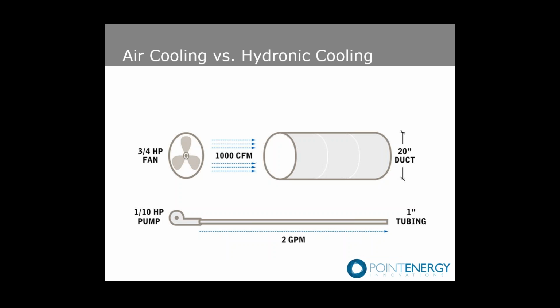What this results in is that a 3/4 horsepower fan will do the same amount of cooling work as a 1/10 horsepower pump. So in terms of energy, that's a pretty big win.